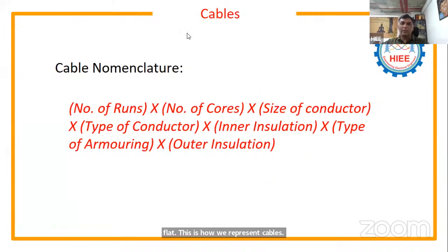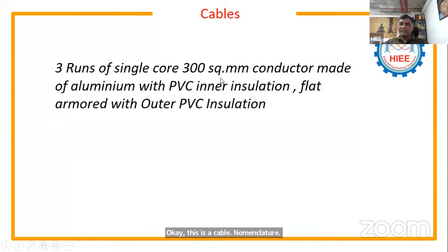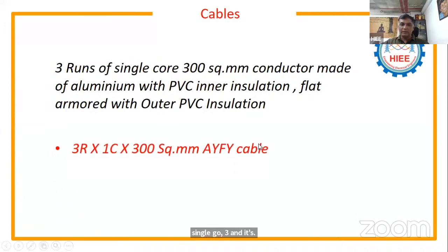This is how we represent cables. Okay, this is cable nomenclature. Before going to understand the sizing calculation and all, these are very important things, and we'll discuss LSH and FRLS and all. Okay, 3 runs of single core 300 square mm conductor made of aluminum with PVC. That's what I explained now. And here, 3 runs of single core 300 square mm AY-FY cable. So what do we mean by this? 3 runs is 3 cables of single core. Single core means each phase, R, Y, B, has 1 core connected, and 300 square mm is the conductor size. AY-FY is aluminum conductor with PVC inner insulation, flat armoring and PVC outer insulation.